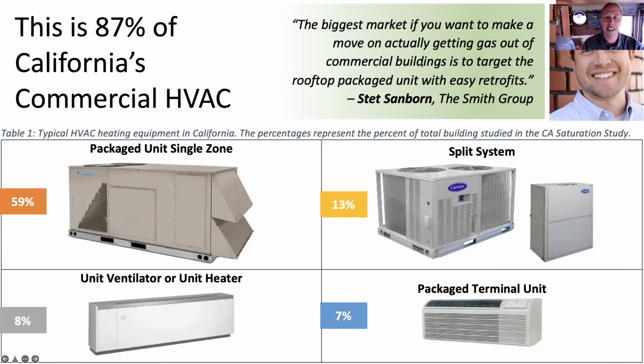As he says, the biggest market if you want to make a move on actually getting gas out of commercial buildings is to target the rooftop package unit with easy retrofits—you take one package out, you put another package in. Slightly more complicated is the 13% that are split systems, because frequently you have to replace essentially everything: the system up on the roof, and the refrigerant line that goes to the fan coil, which is this box here—this looks like a ducted system. Then unit ventilators or unit heaters make up about 8%.